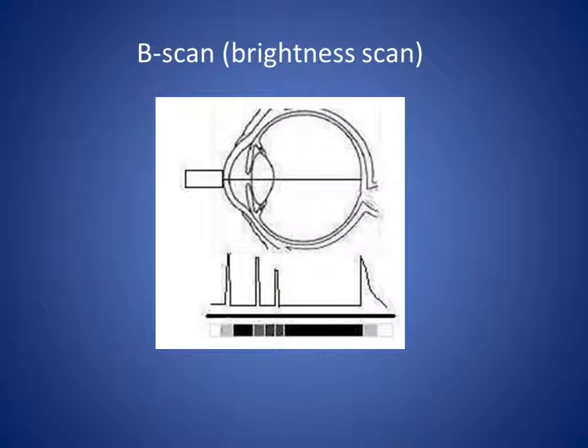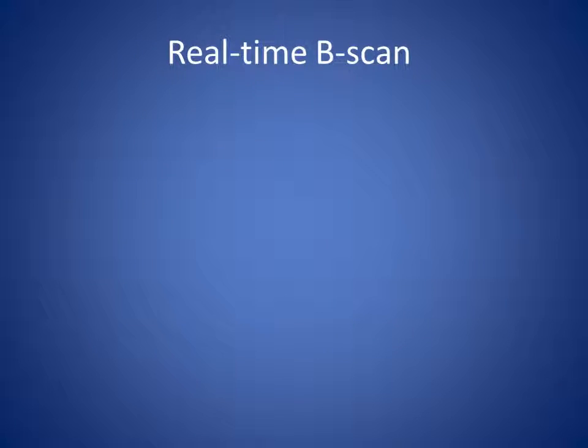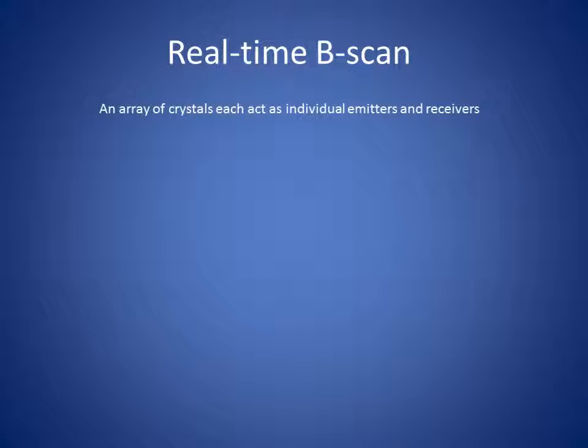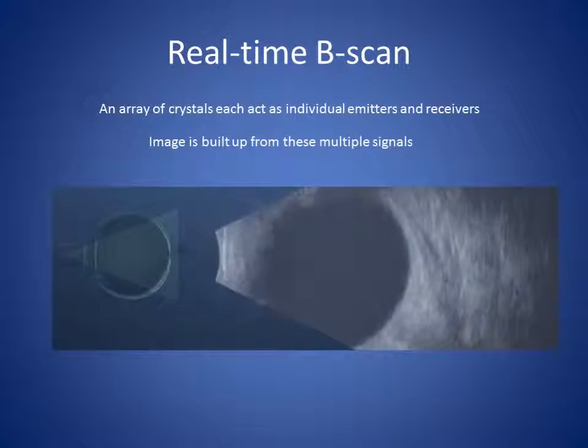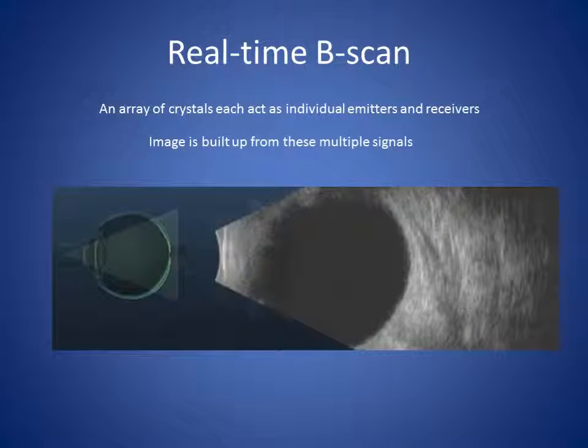The area that does not give rise to any spike — for example, in the eye, the aqueous and the vitreous — will appear black. The corneal spike and the retinal spike in this image have the biggest amplitude and therefore appear nearly white. In modern ultrasound scanners, an array of crystals in the ultrasound probe each act as individual emitters and receivers. The signals from each crystal are processed and constructed into the final, real-time image on the screen.